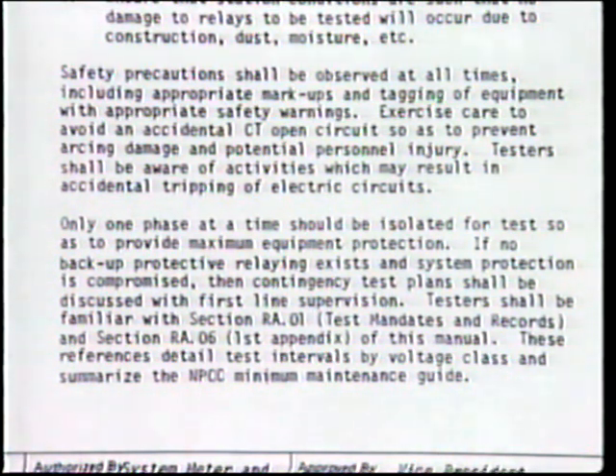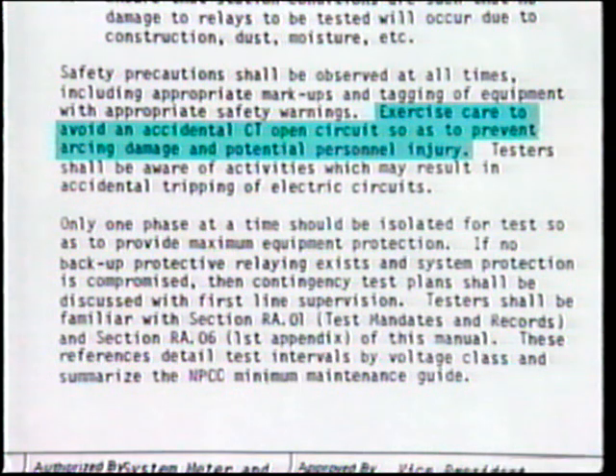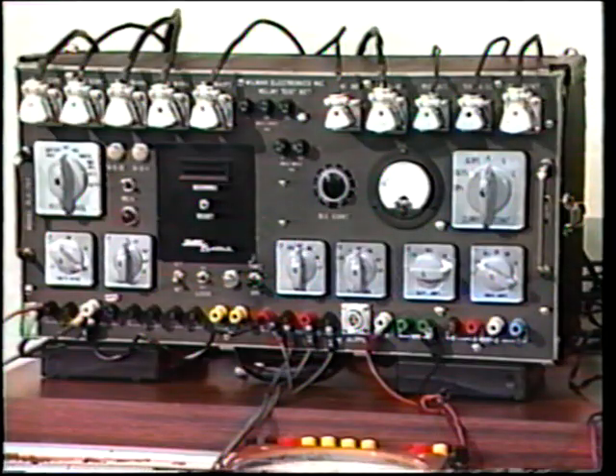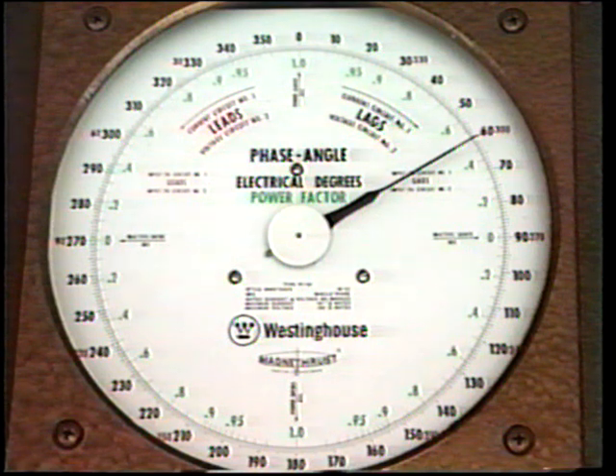First, a general warning about safety. One item, for example, is the need to look out for open-circuited CT secondaries. Attention is drawn to test instruments. Usually, a list is provided according to the particular type of protection scheme. One important point here is that test instruments must be calibrated and be of a level of sensitivity and accuracy which is higher than the tolerance permitted on the equipment under test.